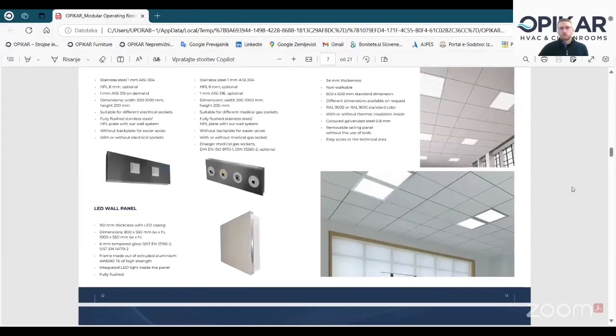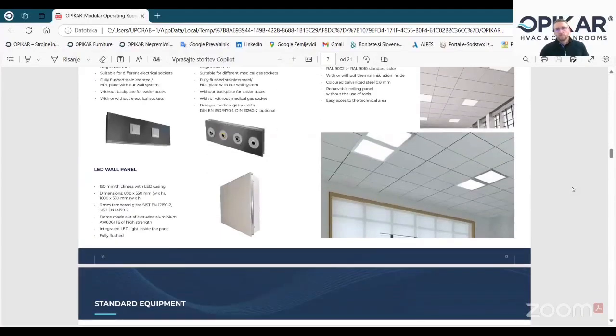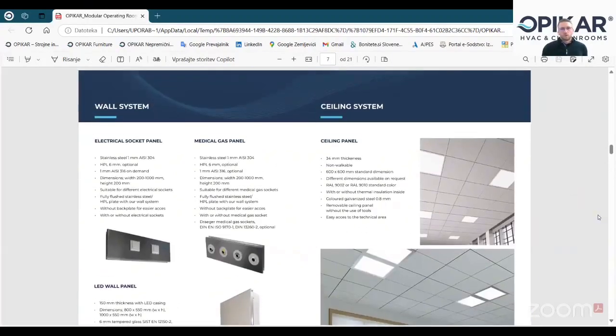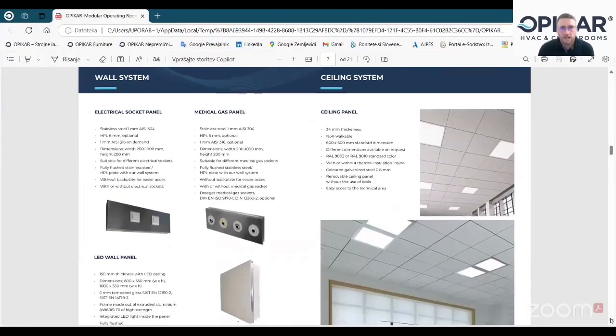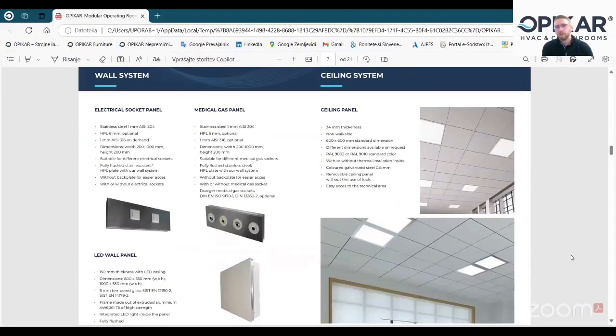The next thing that we also produce is the ceiling for the operating theaters. Normally galvanized steel is used. It can also be stainless steel, painted or not. This is always an option that you can choose. The panels are 60 by 60 centimeters, and they are totally removable. It's easy access to the technical areas, and in operating theaters this is a mandatory thing, because from above there's no option to come near the elements that you want to service.